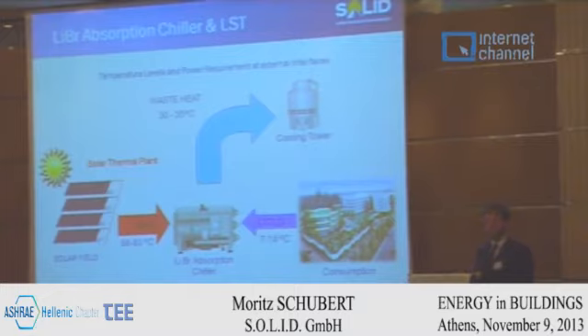Here I give you a small insight into the temperatures operated. For the absorption chiller machine, this absorption process is very sensitive to temperature levels. So on the cooling side, on the building side, it should be a building at a rather high cooling standard, where you can go into the building at 14 degrees, at 7 degrees, or let's say maybe also 6 degrees, but it shouldn't require a cold water temperature of, let's say, 3 or 4 degrees, because here the efficiency would go down.